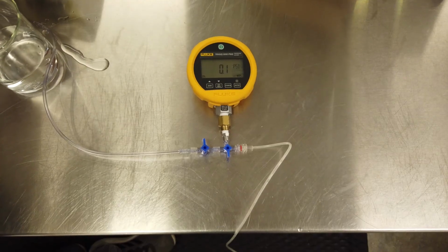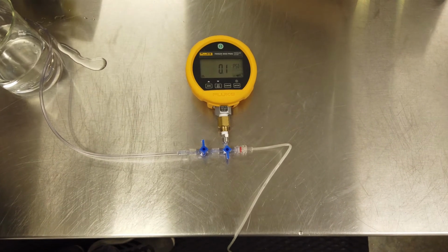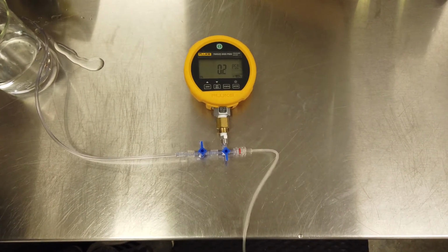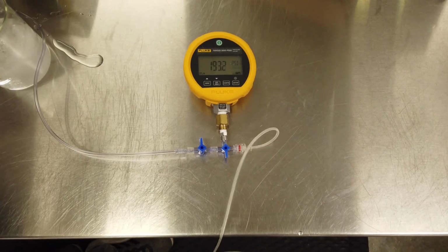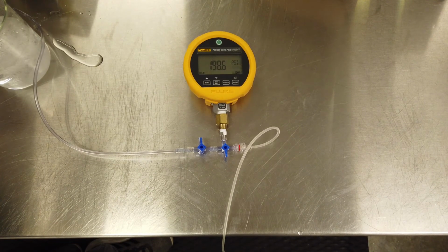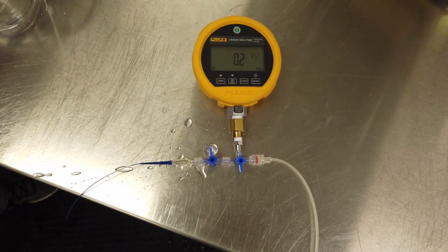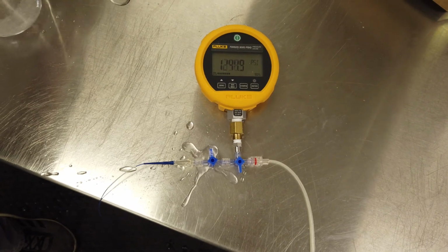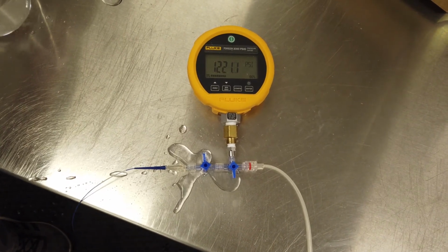Now we are measuring the pressure inside tubing that is used on medical devices. You can see it reaches over 198 psi. When we connect a microcatheter under the same test, the pressure reaches over 1200 psi. You can see that in this case the stopcock fails.